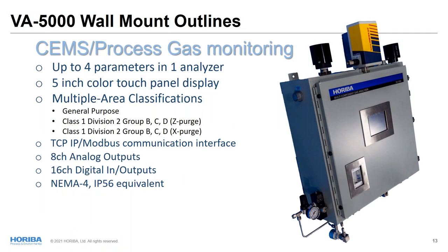All right, here is the outline of the VA-5000 wall mount. As you can see in the picture on the right side, there is the flat 5-inch touch panel screen, which is accessible from outside of the cabinet. And also you can see the Vortex cooler on the top right here. Let me take this laser pointer here. Yeah, this is the Vortex cooler right there. The system on this slide is showing the Z-purge version, and purge gas will be introduced from here.